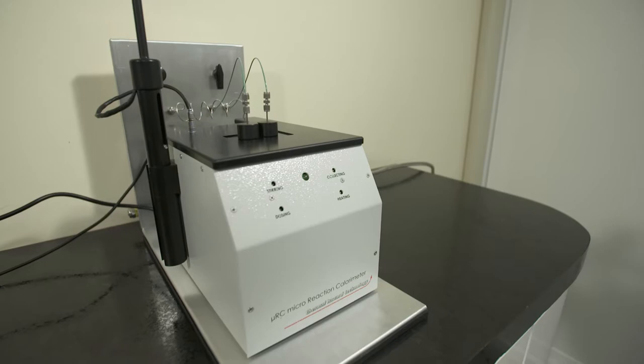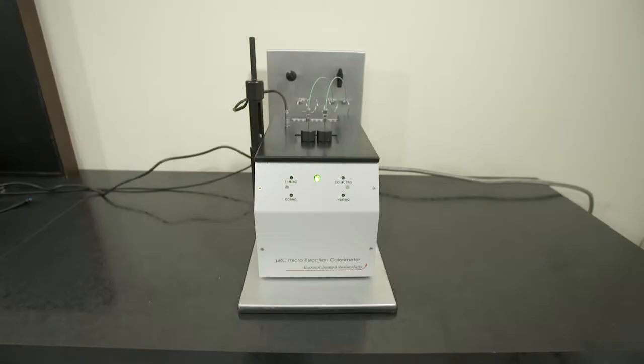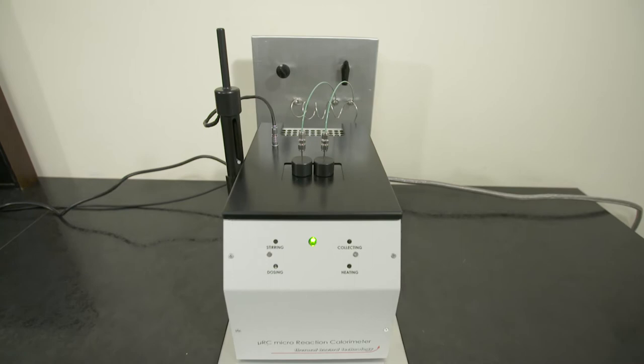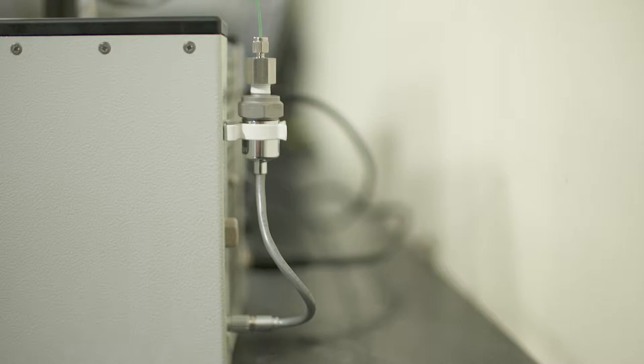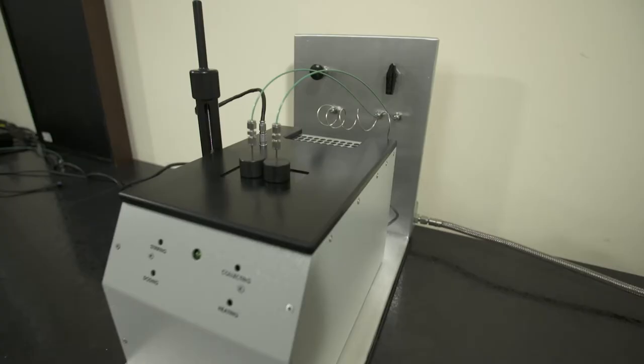The hydrogenation option provides a means for applying an overpressure of hydrogen or other gas into specially designed URC cells. As part of the pressure option, pressure generation up to 30 bar is recorded in stainless steel sample vials connected to the integrated pressure transducer.